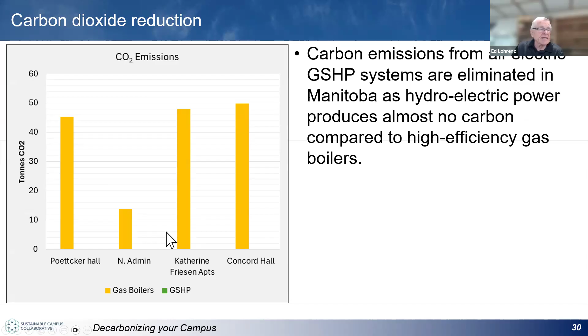So basically, if the designers have done their work properly, you're going to get a good return on the investment, because we can reduce the size and cost of the ground heat exchanger to accurately reflect the building's heating and cooling loads. If you're monitoring it, you can manage the risk, avoid problems, and reduce CO2 emissions. And it does work virtually anywhere in the world.